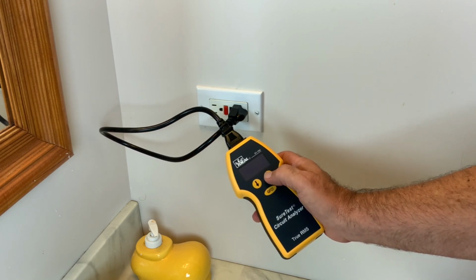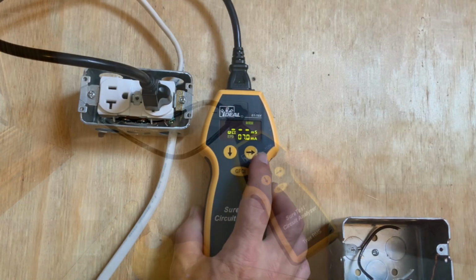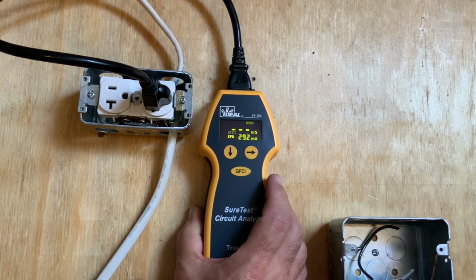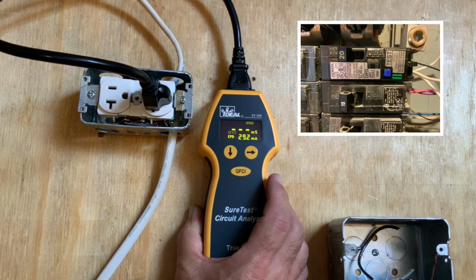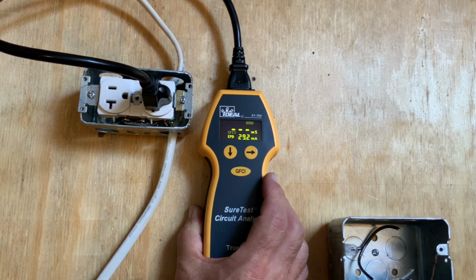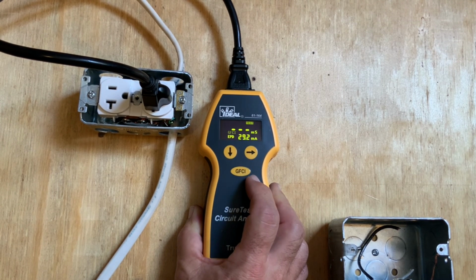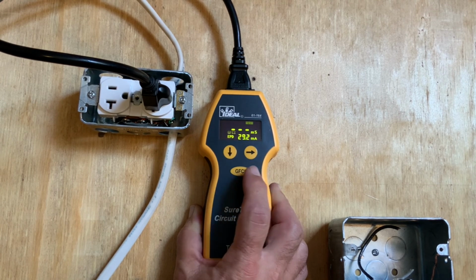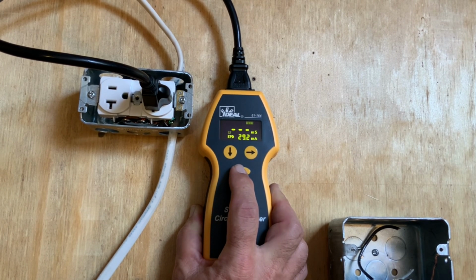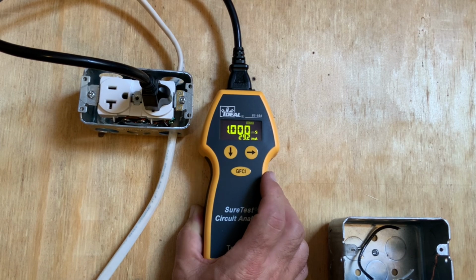This tester will also do 30 milliamp testing, which is called equipment protection devices. You'll find 30 milliamp breakers on things like AFCI circuit breakers that are on the market today. Some of them will have a 6 milliamp GFCI built into them, and some will have a 6 and a 30 milliamp built into them, and some will only have a 30 milliamp test built into them. But this tester will allow you to test the 30 milliamp trip function that is found on many circuit breakers today.